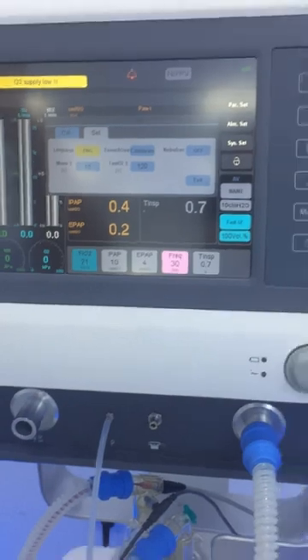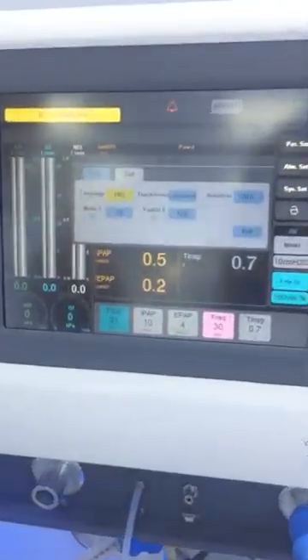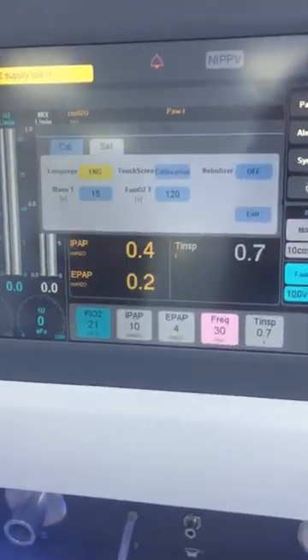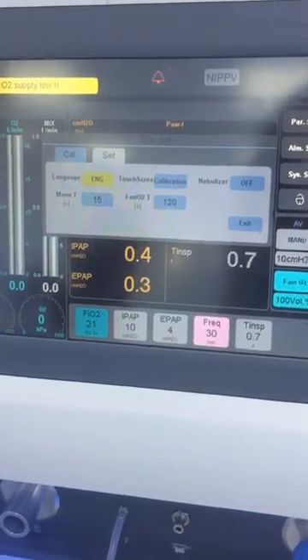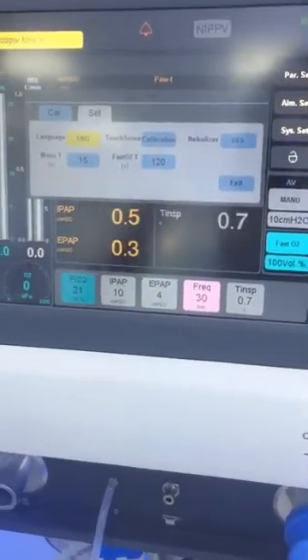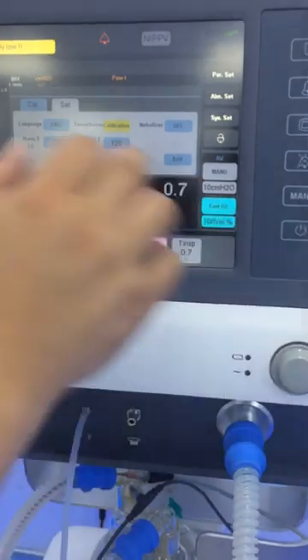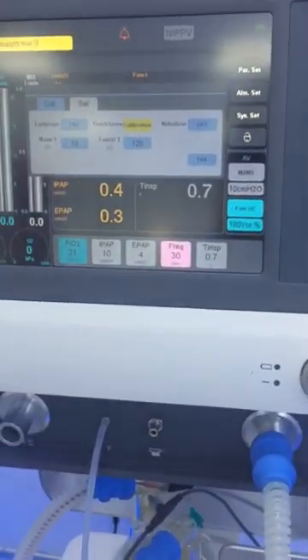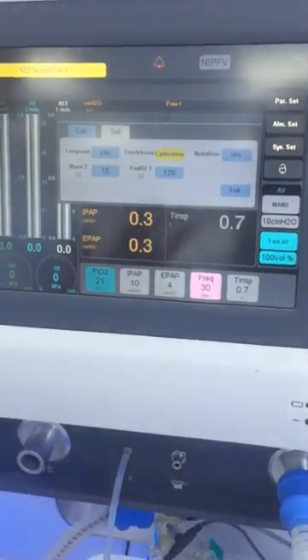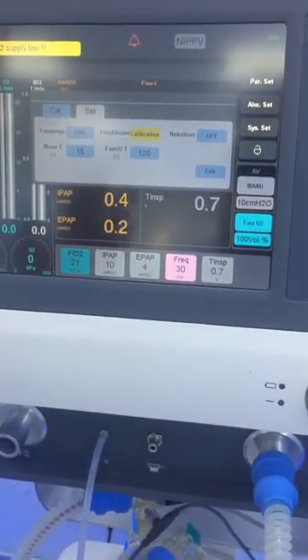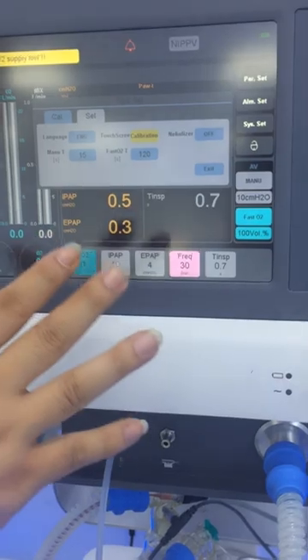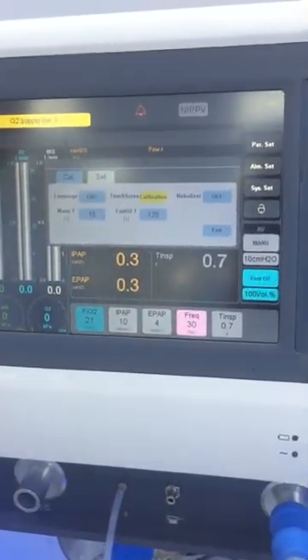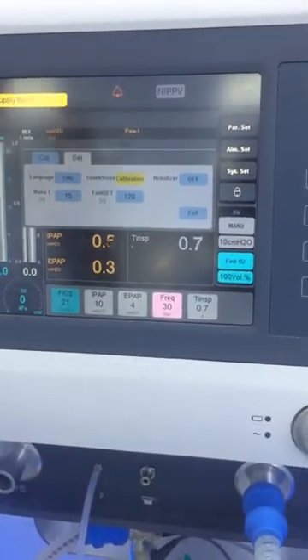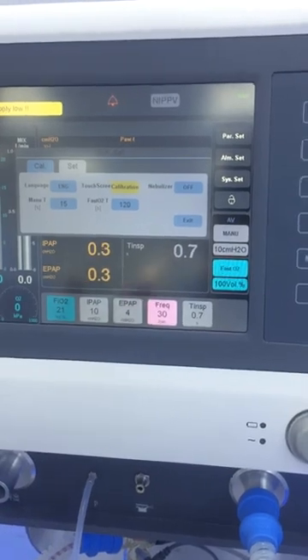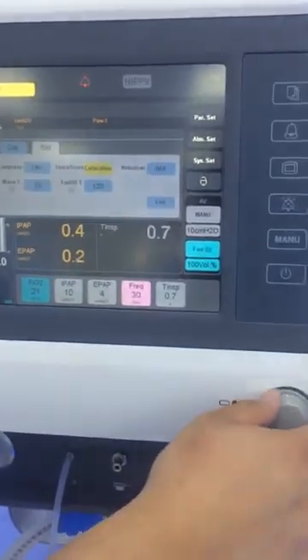The set here is for the language, because for this machine in different countries we have different languages to be suitable for the patient to use. So you can choose here, and also here we have the touch screen calibration. That means for this machine, even after many years, if you think the parameters or the calibration are not very accurate, we can do all the calibrations on the screen by the doctor's hand or by the patient or even by the nurse. Very easy. No need for sending the engineer to the hospital.